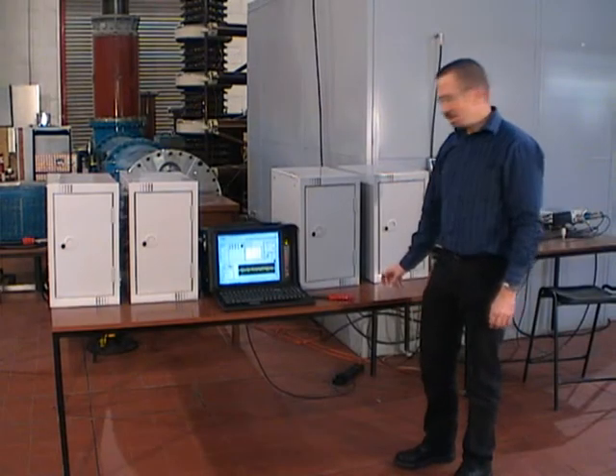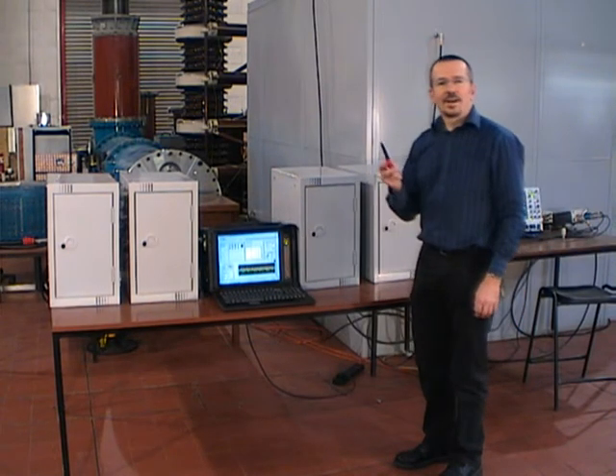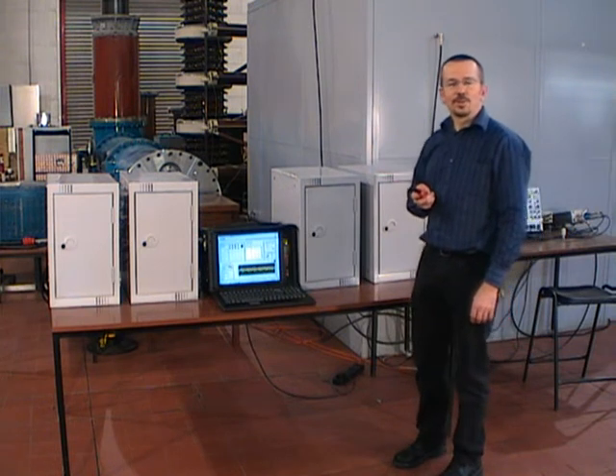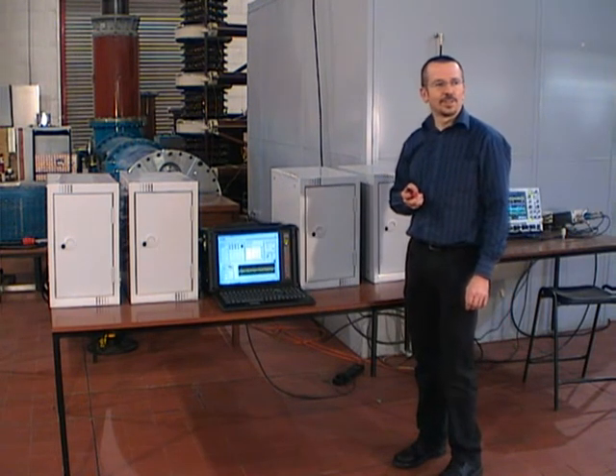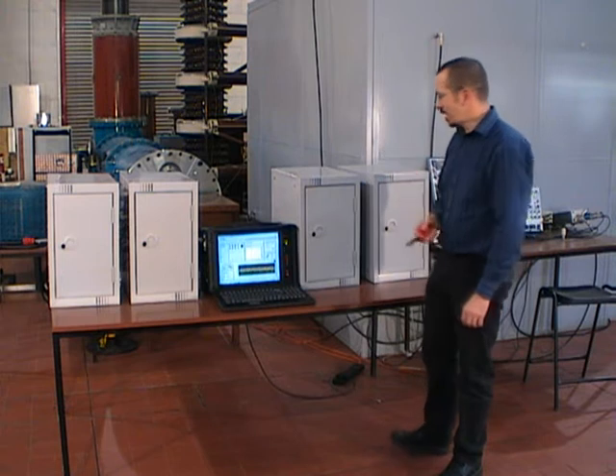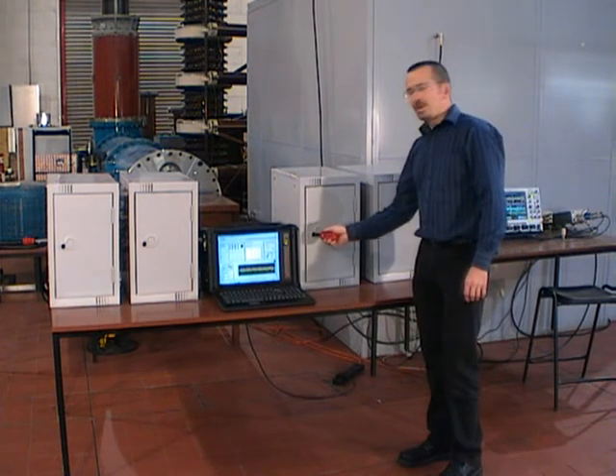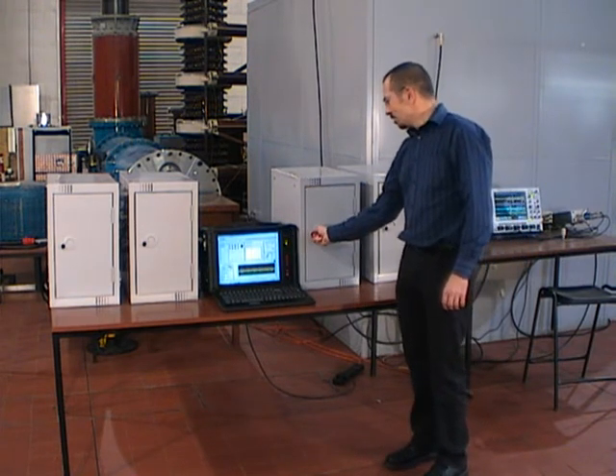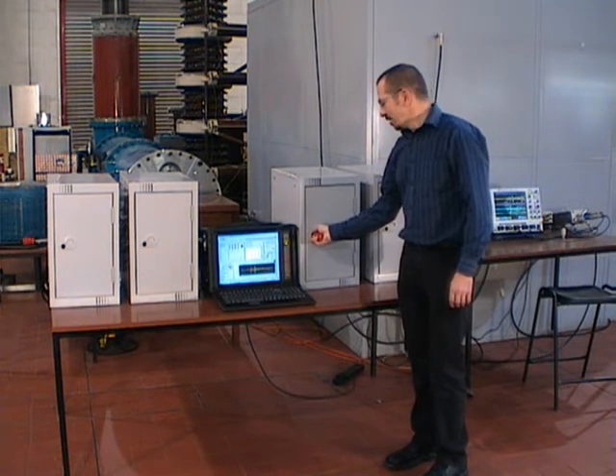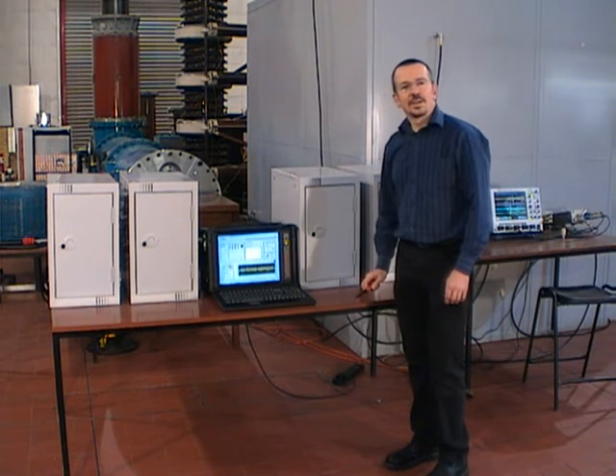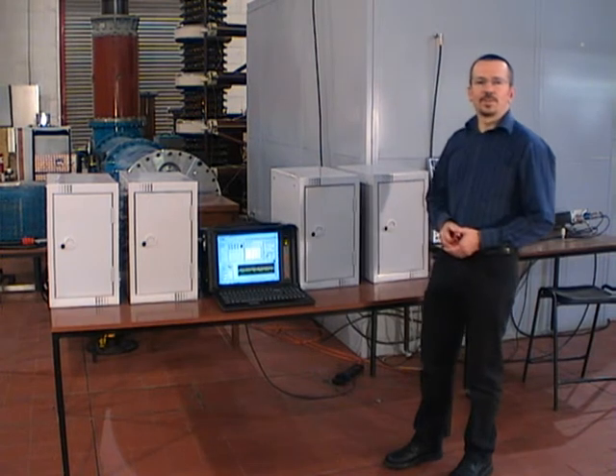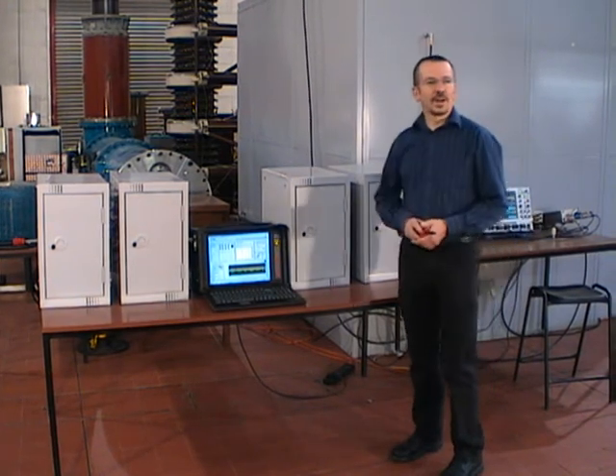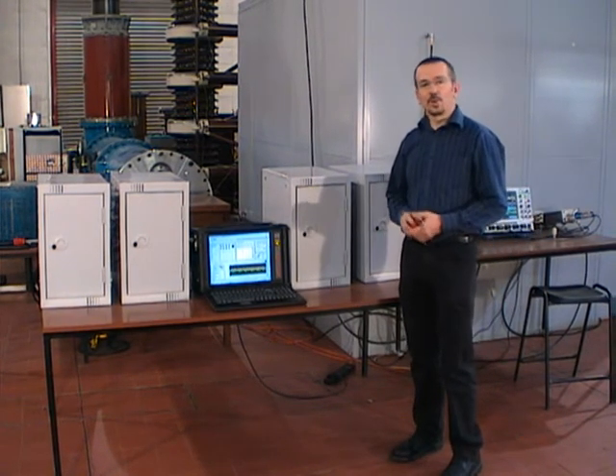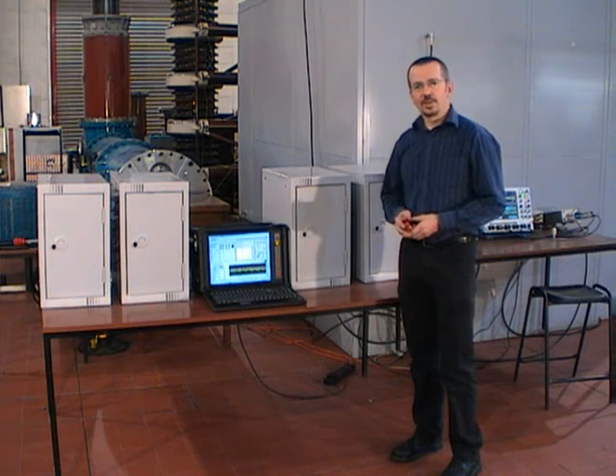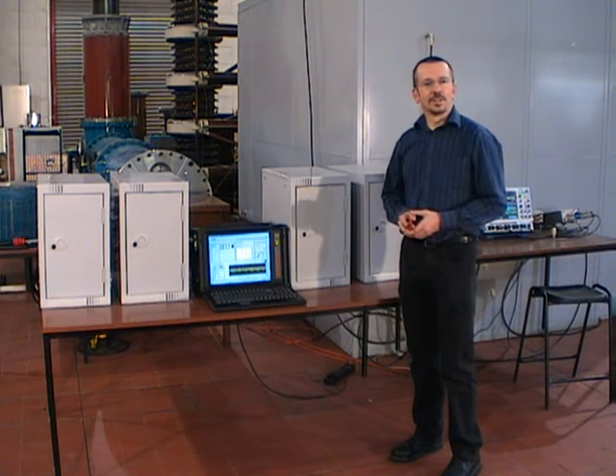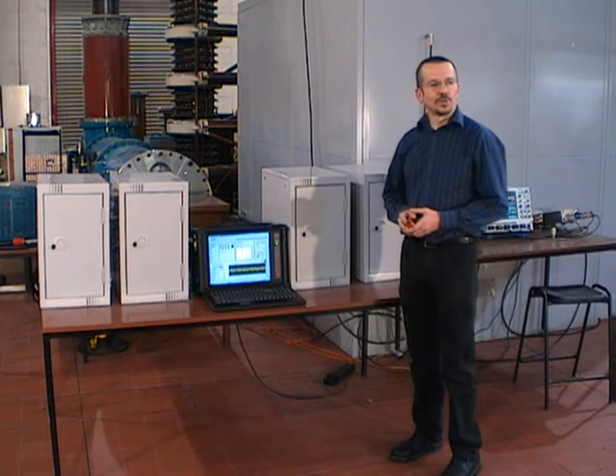For the purpose of demonstrating the system, a handy device to create a spark similar to a partial discharge or low-level arcing is a piezoelectric lighter. So if we insert that into one of the boxes here and fire it, the system picks up the RF signals radiated by the spark, and identifies that there has been a partial discharge event, and also which piece of equipment it's associated with, so that it can be logged in a file for storage and analysis later.